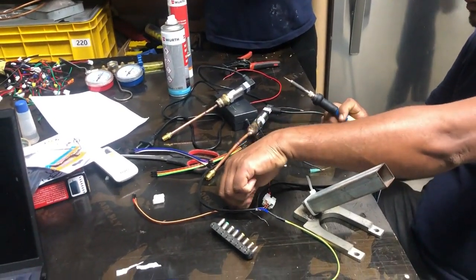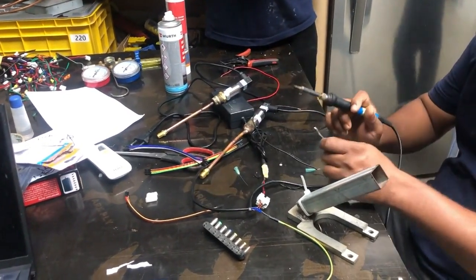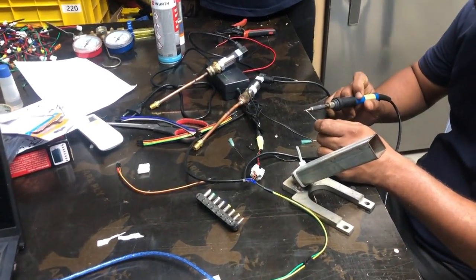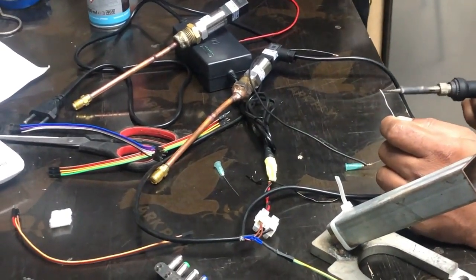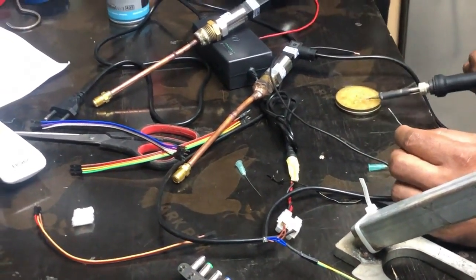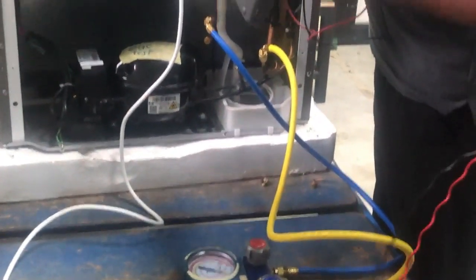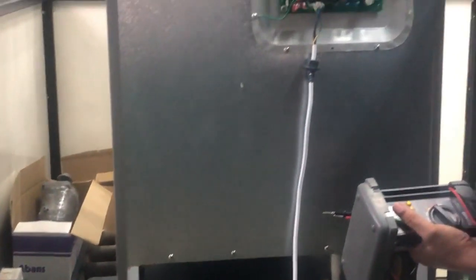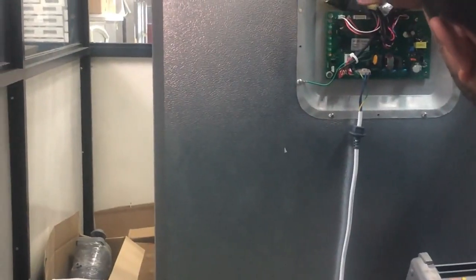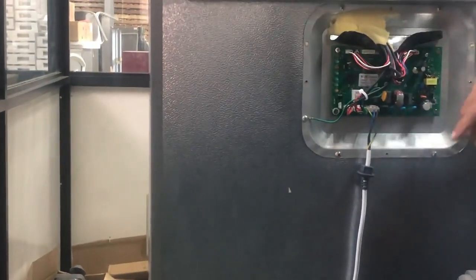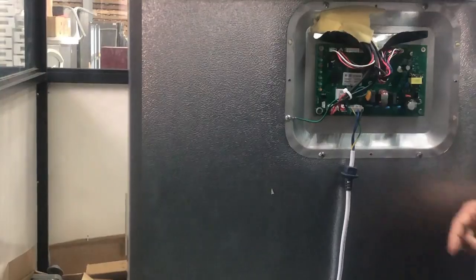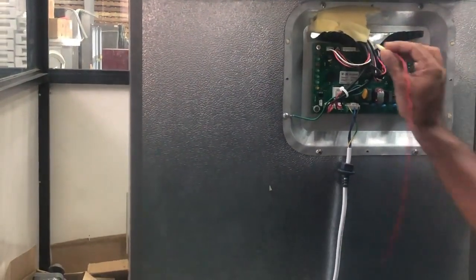Another crucial task was measuring the compressor speed. For this, we used two needle probes connected to a frequency meter. These needles were plugged into the wires, transmitting pulses to the compressor, bypassing the signals from the refrigerator's controller. This method allowed us to monitor the compressor's operational speed accurately.